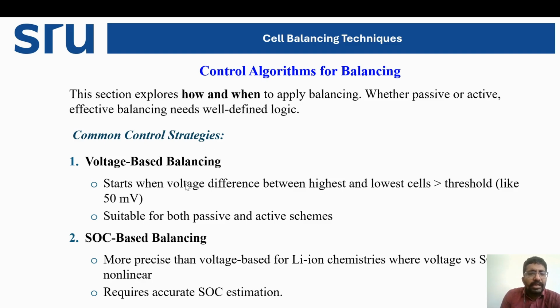So common control techniques, like voltage based balancing. What happens in voltage based balancing? It starts when the voltage difference between the highest and lowest cell is greater than a threshold, say 50 millivolts or 100 millivolts. This difference in voltage initiates the balancing process, which is why it is called voltage based cell balancing. Voltages need to be monitored, and once the difference between any two cells exceeds the preset threshold, we start the process of cell balancing.